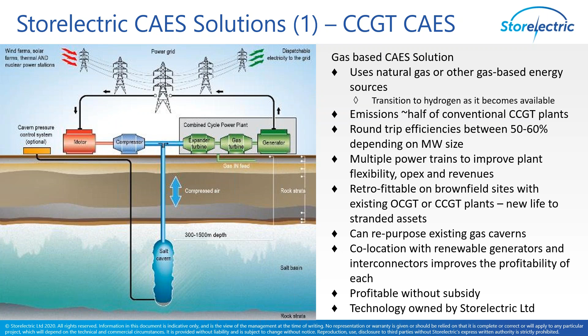Our second technology actually addresses the question of heat. Instead of wasting the heat up a cooling tower, we put the heat into storage. When we need to expand the air to generate electricity, we put the heat back into the air during that process. That increases the grid-to-grid efficiency I talk about—not like batteries, which only talk about terminal-to-terminal efficiency. Big difference. Grid-to-grid efficiencies are up about 70% at scale. These systems scale from 40 megawatts up to multiple gigawatts, for a duration of 4 hours and upwards, making it vastly more profitable, at a similar cost to existing compressed air energy storage.